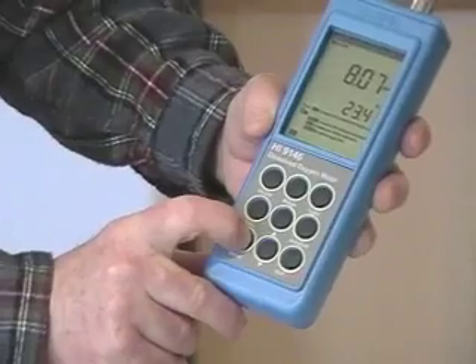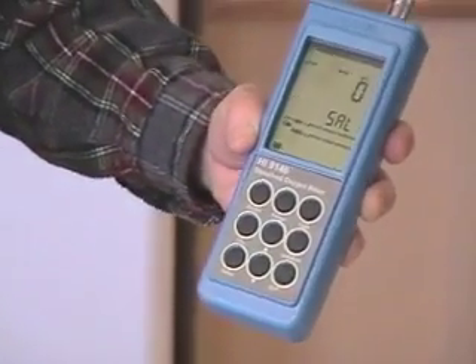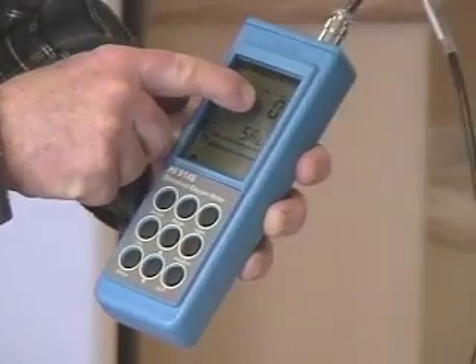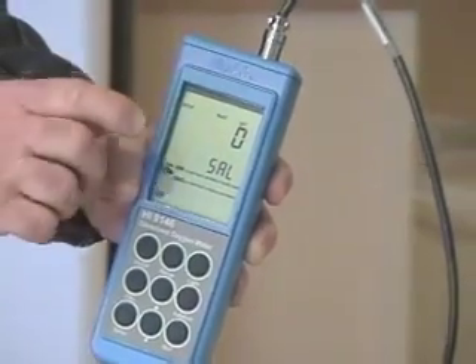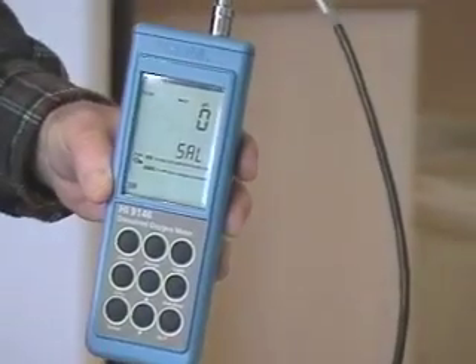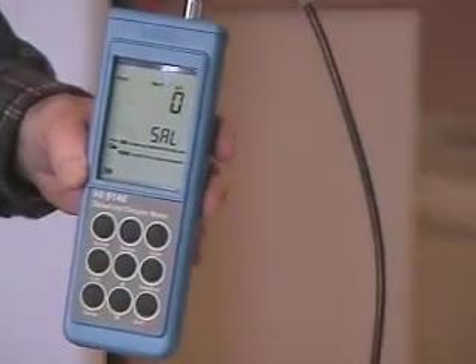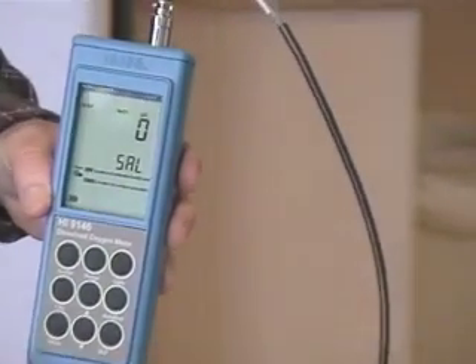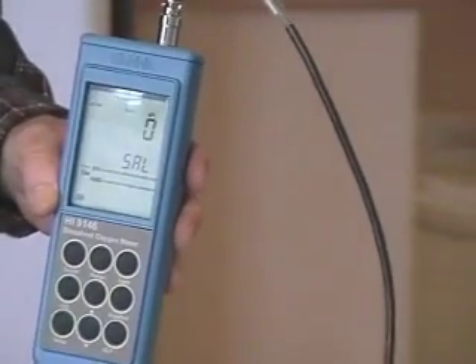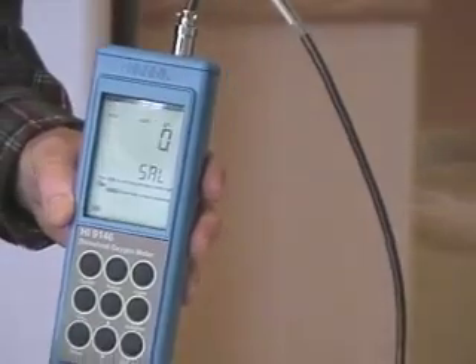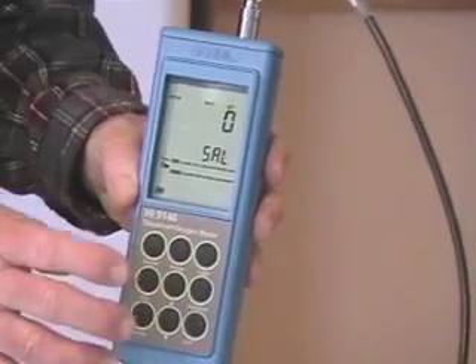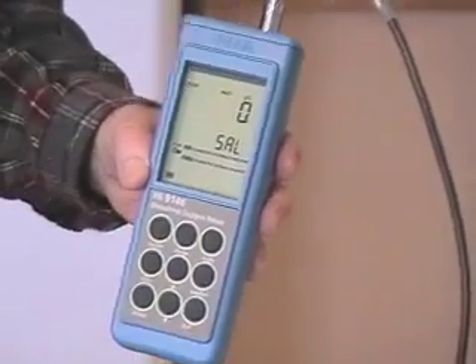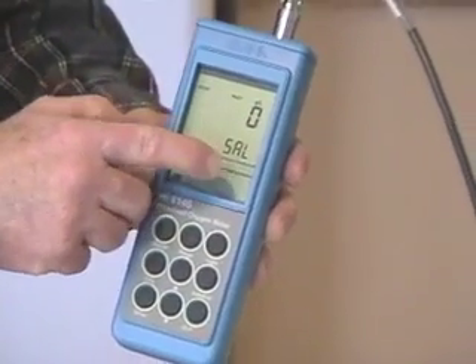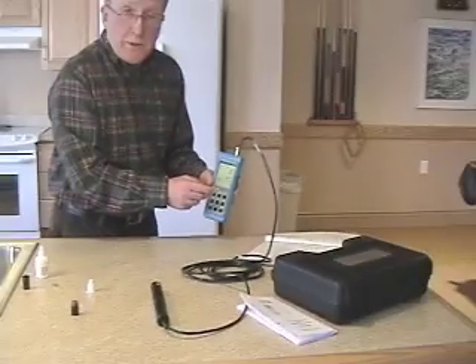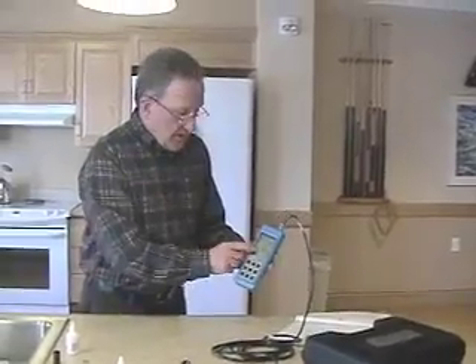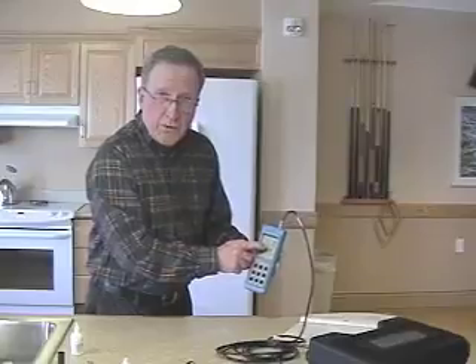You push the setup button, and the first parameter that comes up is salinity. The salinity is expressed in grams per liter, okay? And it has defaulted to 0. You need to calibrate the meter as close as you can to the salinity and the altitude of your sampling point. For our purposes, we're in an area where the salinity is very low, where it's all fresh water. When you do measure salinities, they're expressed in milligrams per liter, and they're very, very low concentrations. This is expressed in grams per liter. That is 1,000 times more concentrated than the milligram per liter. So for all intents and purposes, it's a 0. So we're going to leave the salinity mode here at 0 grams per liter.